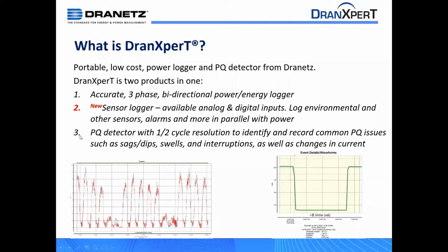Well, the third here, it is a PQ detector. So in parallel with all of this, DranXperT will detect if there's an RMS power quality event. And that's the example you can see down here on the right, where the voltage dipped down for a period of time and then went back up again. Just please don't misunderstand. This is not a PQ meter. It's not going to give you the oscillography and all the wave shapes and stuff. It's just kind of set off an alarm. Hey, you got a PQ problem.